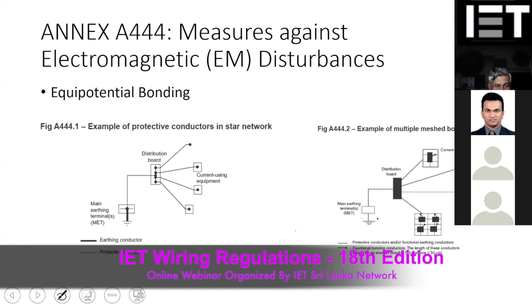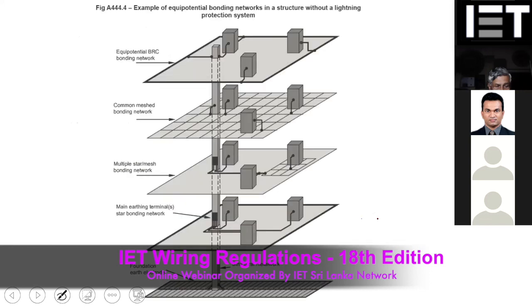In early days, people were talking about your power earth, your telecom earth, your lightning arrestor earth, and so on. Likewise, the clean earth, dirty earth, the different types of earthing. Now those concepts are no longer applicable. The new standards do not recognize them like that. What you have to have is equipotential bonding, so that you have the same potential, even for the lightning arrestor, the telecommunication, the power earth, everything. You have to have the same potential everywhere within the premises or building.